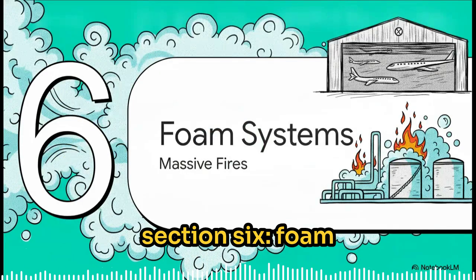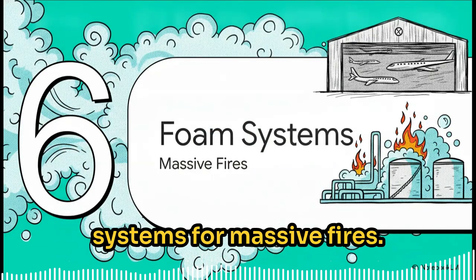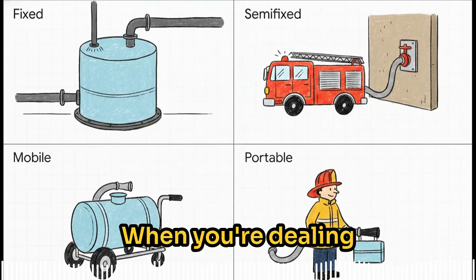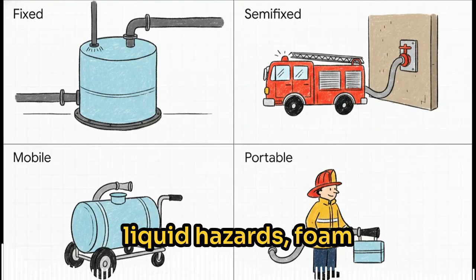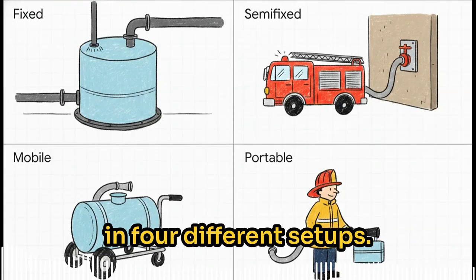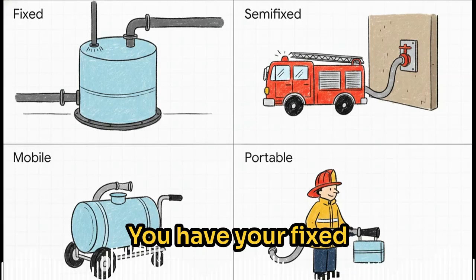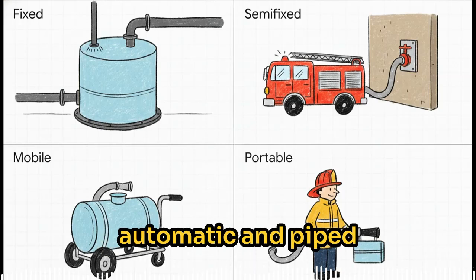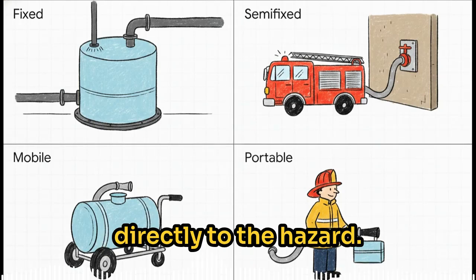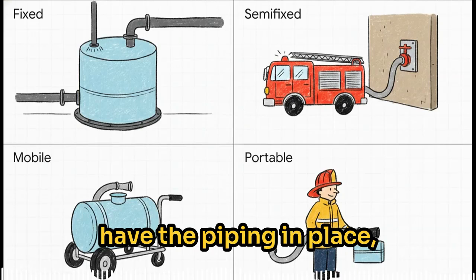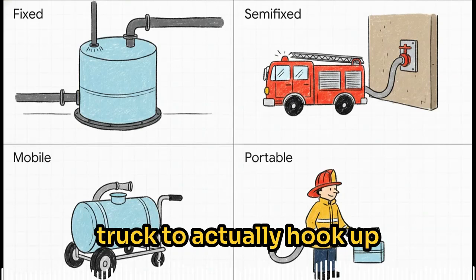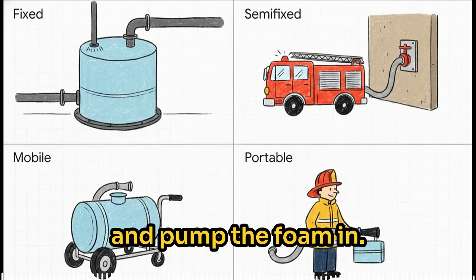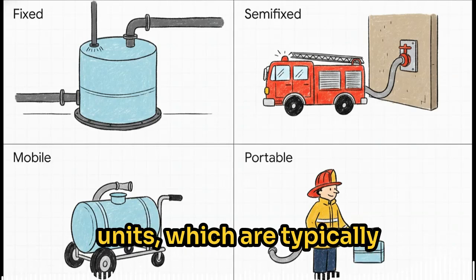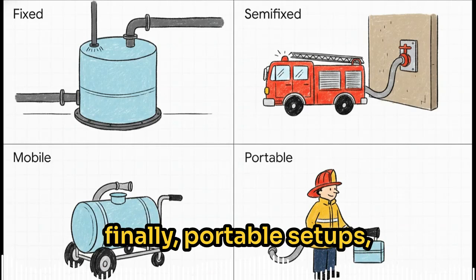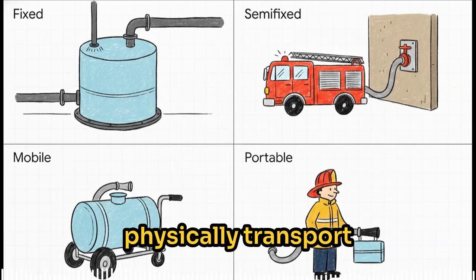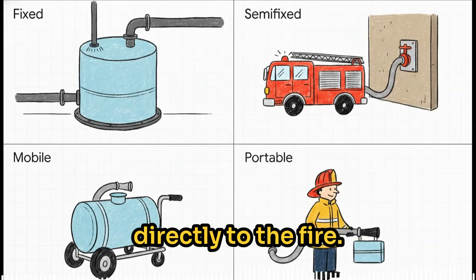Section 6, foam systems for massive fires. When dealing with massive flammable liquid hazards, foam systems are deployed, and they come in four different setups. You have fixed systems, which are fully automatic and piped from a central station directly to the hazard. Semi-fixed systems have the piping in place but require a fire truck to hook up and pump the foam in. Then there are mobile units, typically wheel-mounted, and finally portable setups, where trained personnel physically transport the hoses and nozzles directly to the fire.